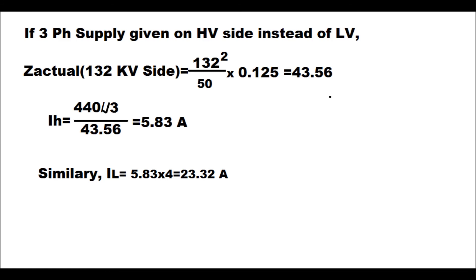Instead of giving supply on the LV side, supply can also be given on the HV side. However, in that case Z_actual comes to 43.56 ohms, the supply current on the HV side will be only 5.83 amperes and on the LV side 23.32 amperes. The secondary currents for HV and LV will be lower. Therefore it is recommended that for the stability test, supply always be given from the LV side so that the current is higher, enabling more accurate measurement of secondary currents.